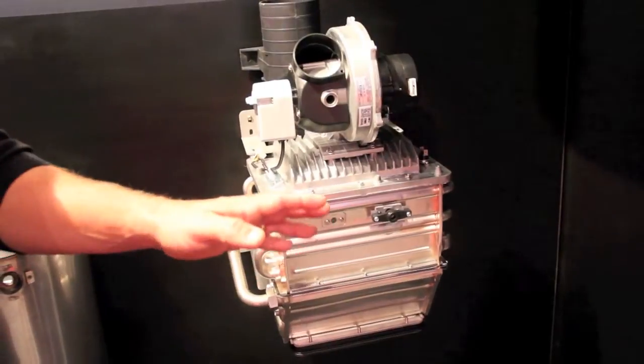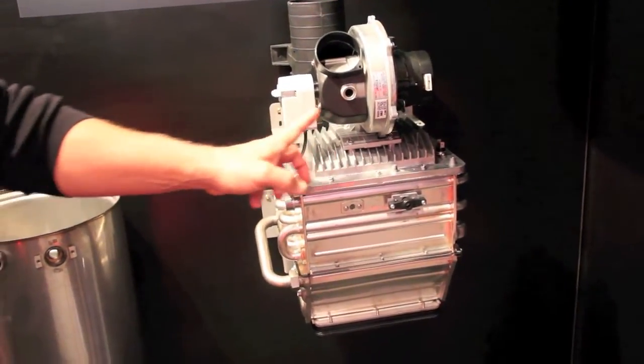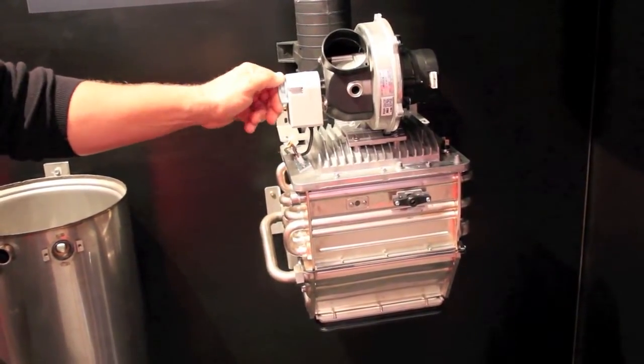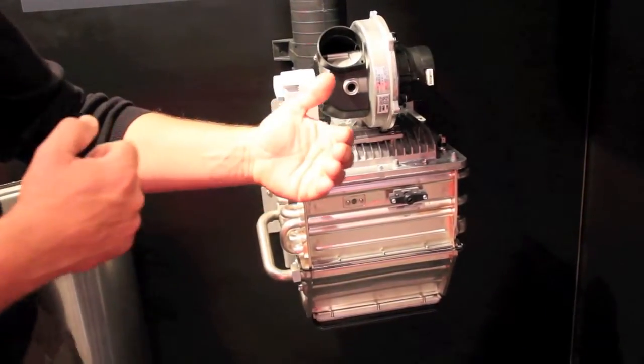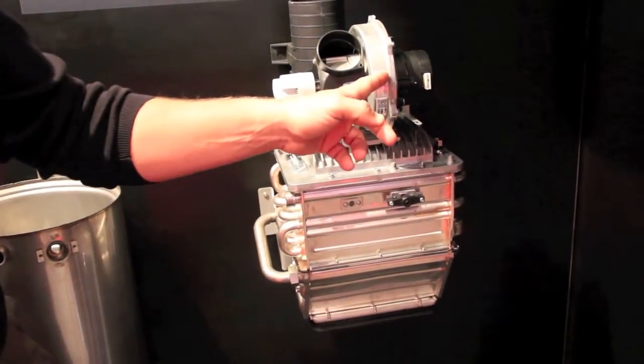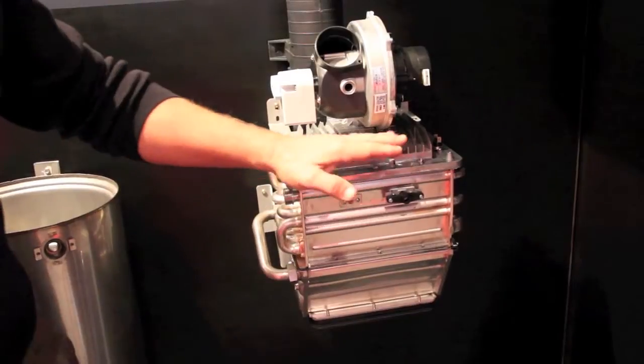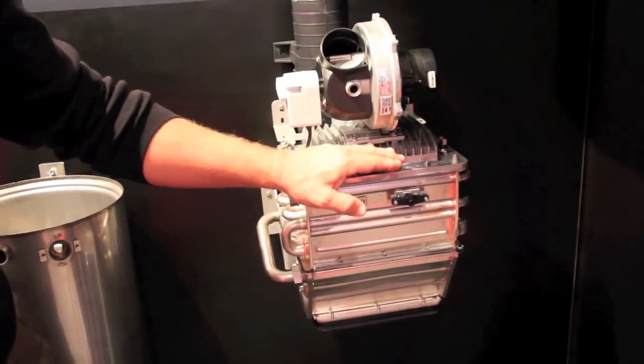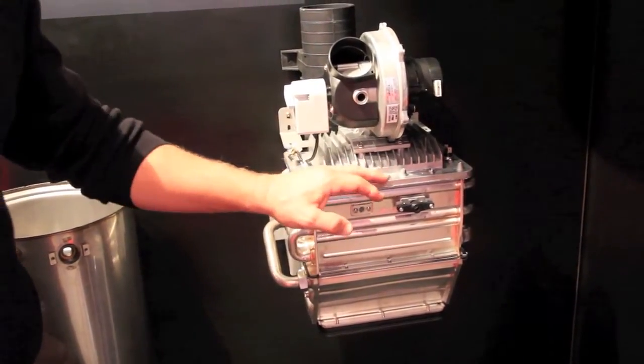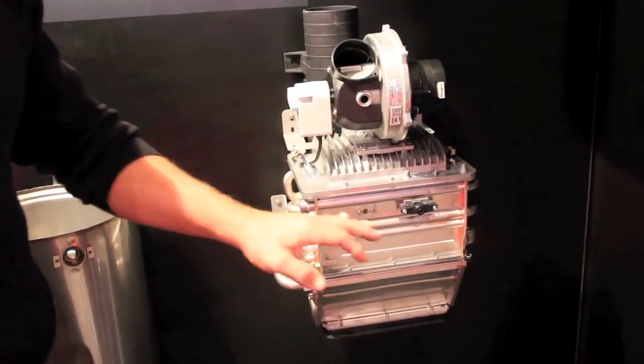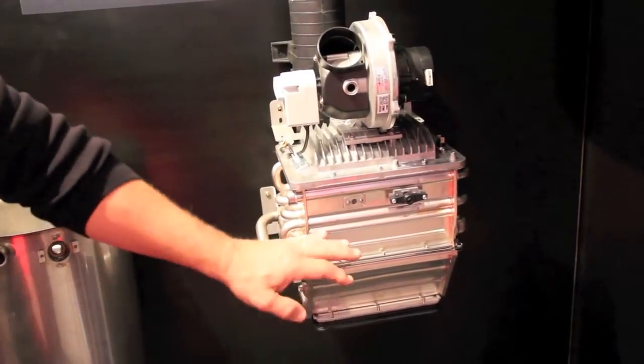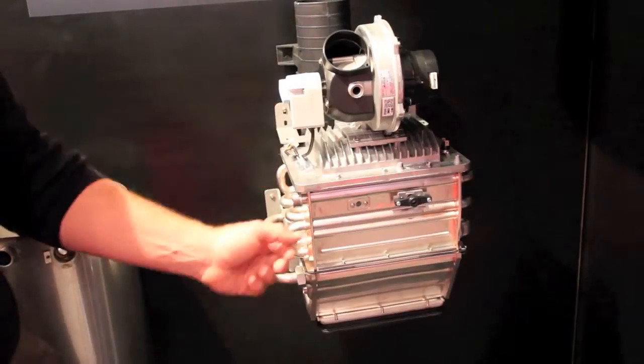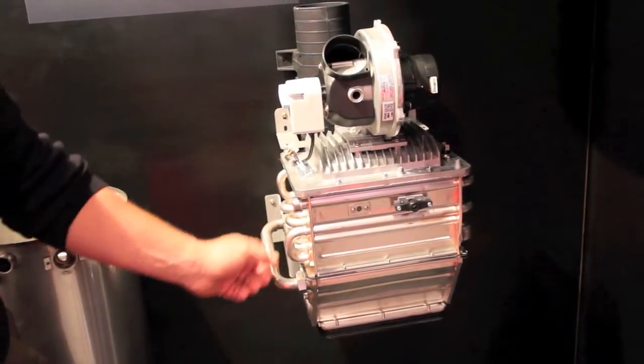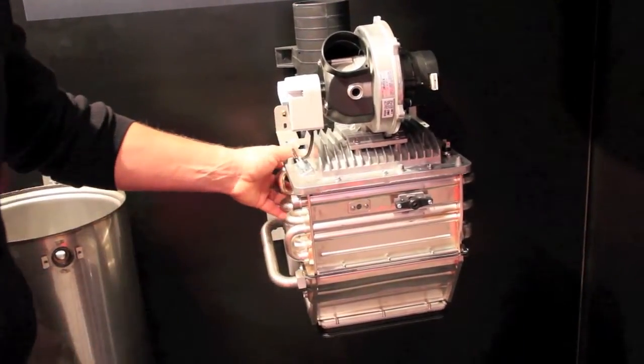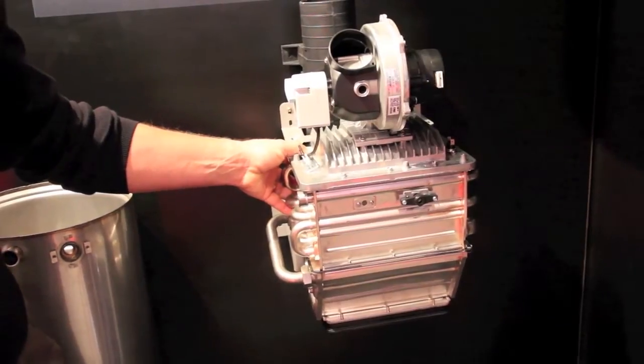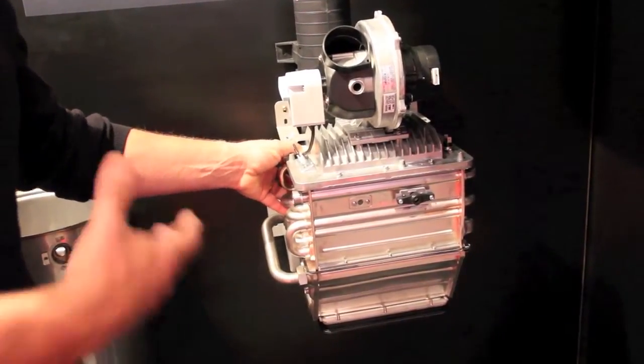It's very quiet operation. The combustion system, as you can see here, has a little stack damper, and this damper basically regulates the amount of airflow going into the combustion system to maintain a very clean burning flame as you start to increase or decrease the amount of hot water you need.